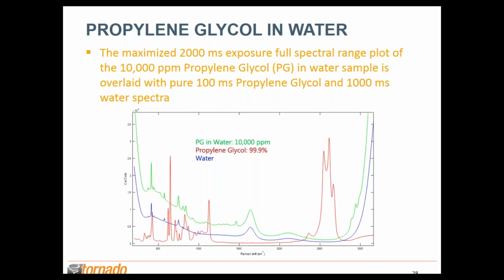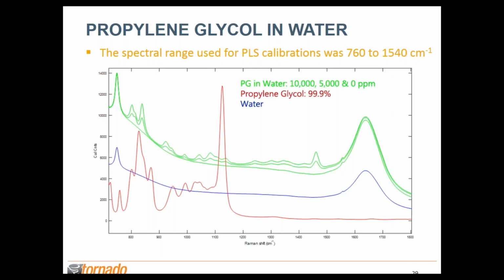We have the spectrum here of the 2,000 millisecond determined exposure for propylene glycol in water, overlaid with the 100 millisecond exposure scan of propylene glycol and the 1,000 millisecond of water. Again, I wanted this for overlay purposes and to help determine the spectral range to use for the PLS calibration. Here propylene glycol is really the primary contributor to the spectral peaks that we've seen, so I could use a larger spectral range, which I did, and it was set to 760 to 1540 wave numbers.